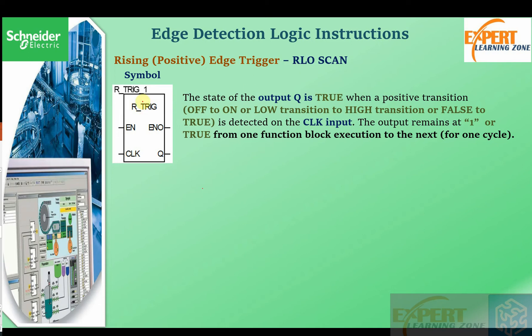Next is a rising edge trigger. R_TRIG stands for rising edge. It says that the state of the output is true when a positive transition — off to on, low to high, or false to true — is detected on the clock input.